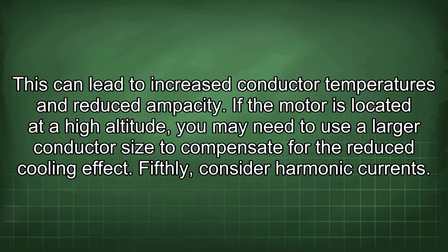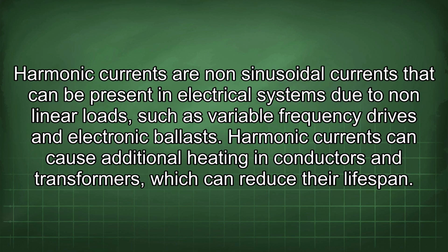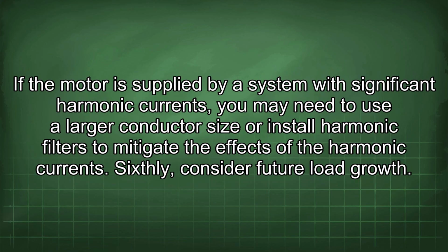Fifthly, consider harmonic currents. Harmonic currents are non-sinusoidal currents that can be present in electrical systems due to nonlinear loads such as variable frequency drives and electronic ballasts. Harmonic currents can cause additional heating in conductors and transformers, which can reduce their lifespan. If the motor is supplied by a system with significant harmonic currents, you may need to use a larger conductor size or install harmonic filters to mitigate the effects of the harmonic currents.